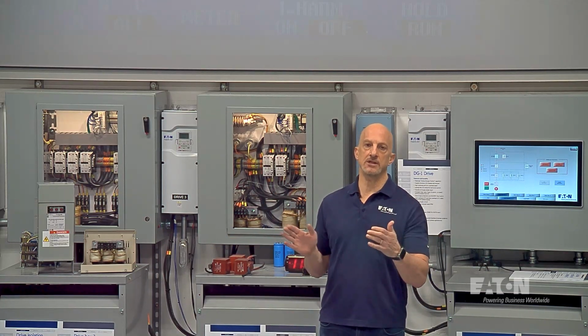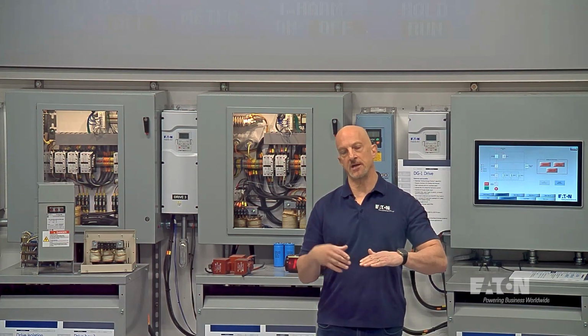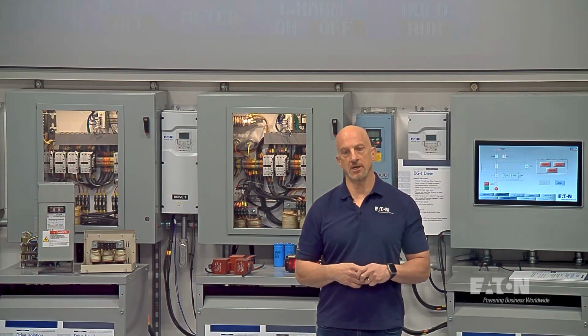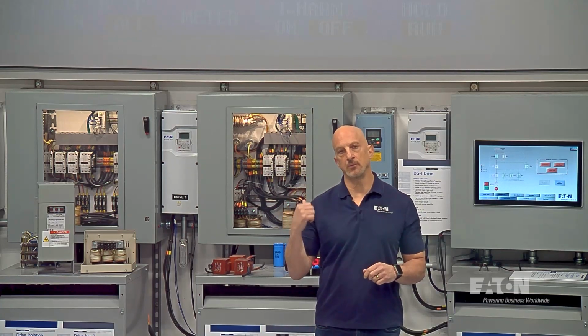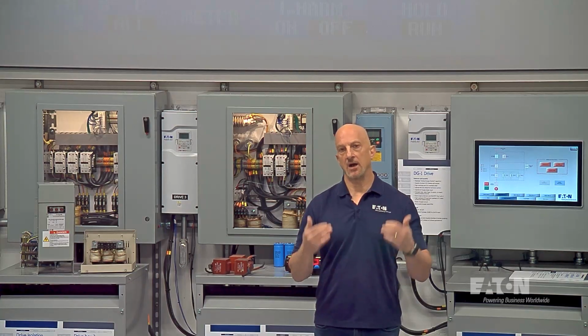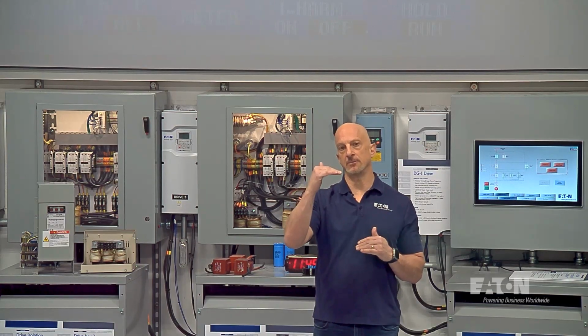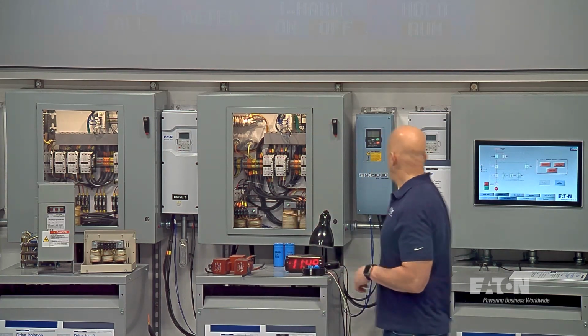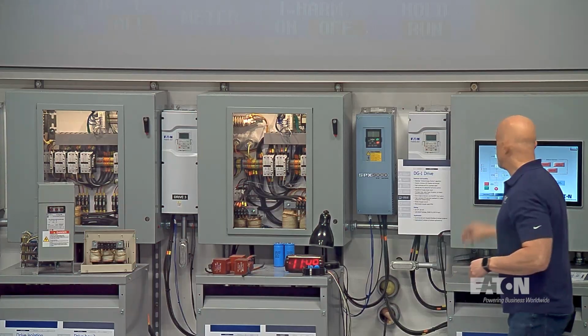And then in between those two, we're going to put on an active harmonic filter, show how the source goes down. We reduce the harmonic currents by injecting equal and opposite harmonics. And then we're going to look at the load right at the drive, and we're going to see how much that actually increases a little bit, and I'll explain why that happens. So let's first of all start up the drive, and we'll run it and take a look at the harmonic current.